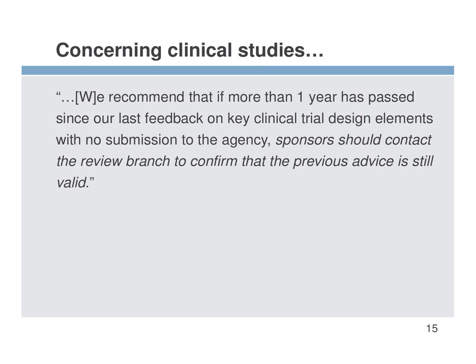And they say this about clinical studies in particular. We recommend that if more than 1 year has passed since our last feedback on key clinical trial design elements, with no new submission to the agency, by that they would mean an IDE submission, sponsors should contact the review branch to confirm that the previous advice, really their advice, is still valid. Just note, I added the italics to emphasize this statement.